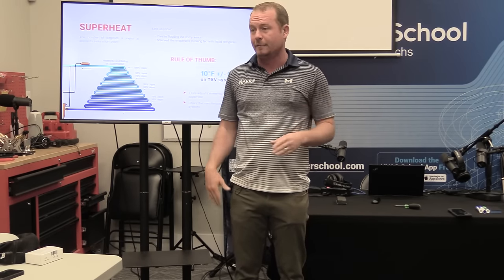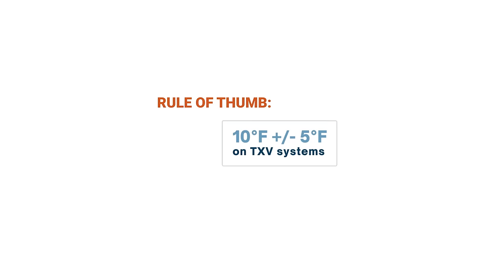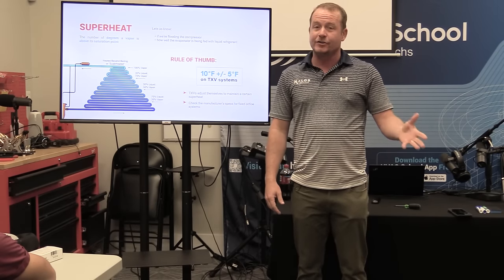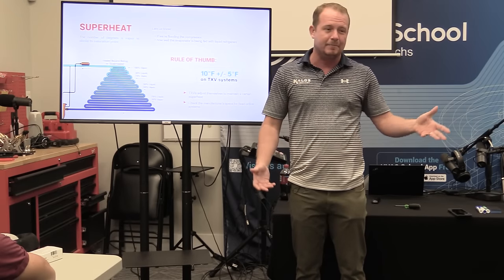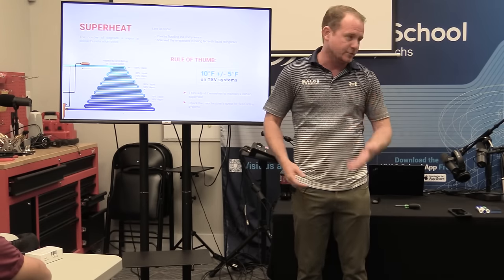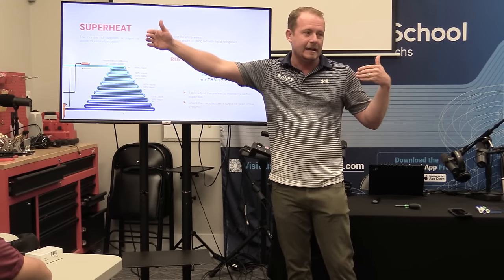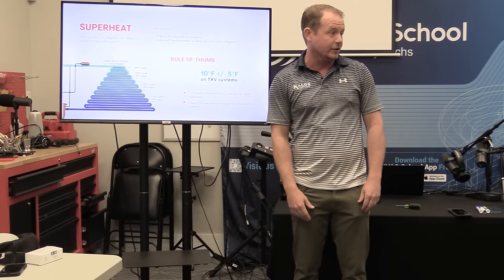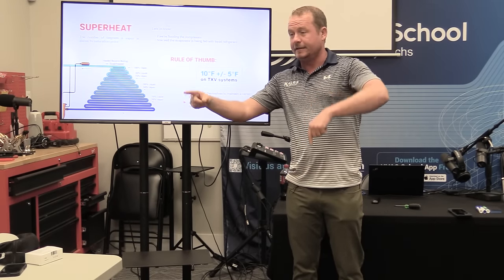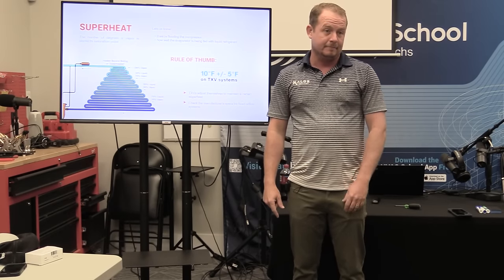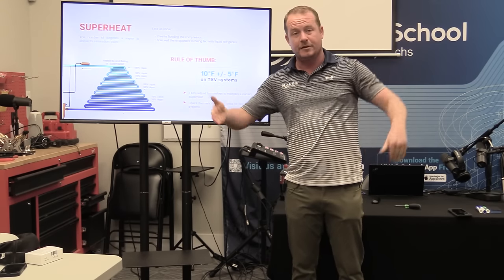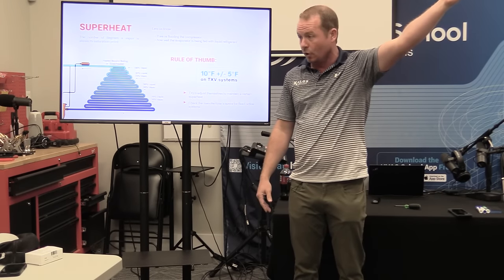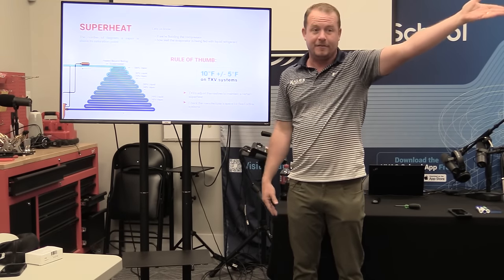On a TXV system, you should expect about 10 degrees Fahrenheit plus or minus 5 degrees — but that's measured inside. If you've got a short line set, suction temperature inside and outside will be pretty close. But if you have a 50, 60, 70, 80 foot line set running through an attic, it's going to be significantly higher temperature at the condenser than at the evaporator coil. Calculate your superheat outside — if you've got 25 degrees outside, look at the difference between suction temperature outside and inside. That difference is an increase in superheat at the evaporator coil. If it's 25 degrees outside and the suction temperature is 10 degrees colder inside, then you've got 15 degrees superheat — you're in line.